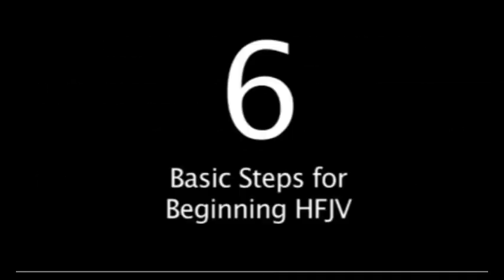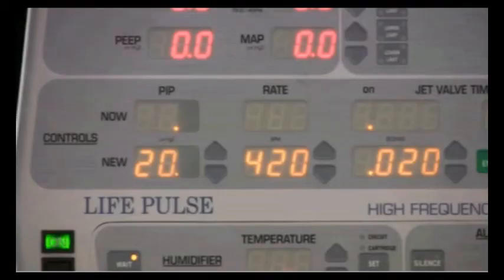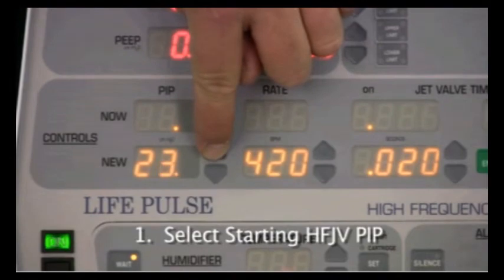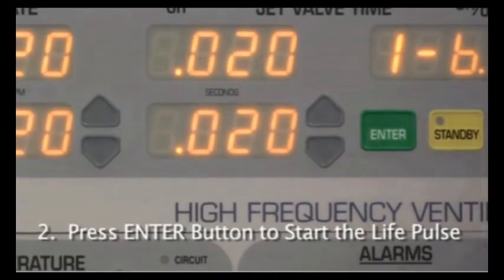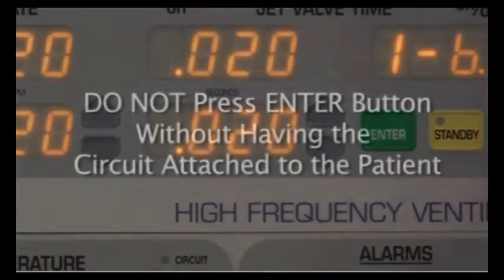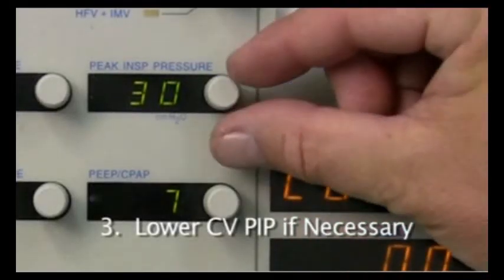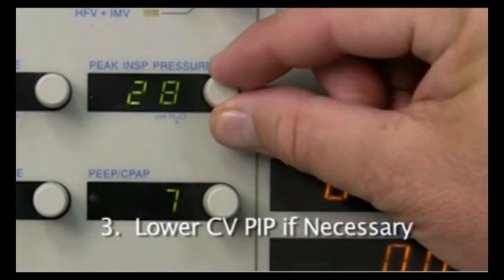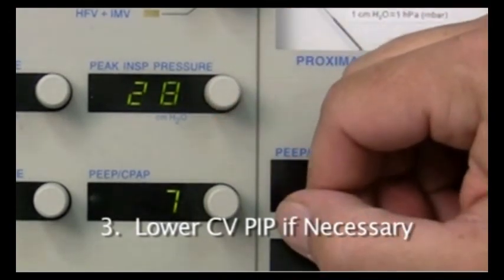There are 6 basic steps for beginning jet ventilation. First, select the starting HFV PIP value. Second, press the enter button to start the LifePulse. Remember, do not press enter without having the circuit attached to the patient. Third, if necessary, lower PIP on the conventional ventilator to prevent interruption of high-frequency pulses.